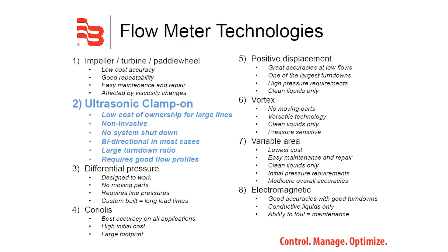Flow meters come in many shapes and sizes with key advantages and disadvantages for each type of technology. For ultrasonic clamp-on flow meters, some of the key advantages are low cost of ownership for large lines, they can be installed without shutting down the system, they can be bi-directional, and have very large turndown ratios.